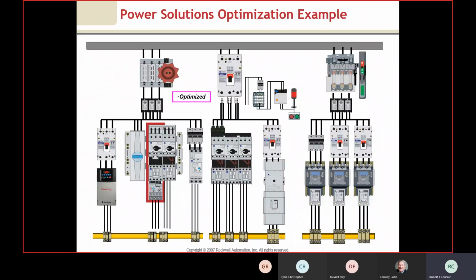This is just an example looking at how we optimized the panels. If we look all the way to the right, we'll notice this is a typical wiring setup: disconnect with the handle to a power distribution block, and then wiring to each one of the starter units. If we look to the left, we'll notice that this was optimized using an NFPA 79 handle to make the closure easier. We're still utilizing a power distribution block here, but now we've stepped down to a MCS bus bar system.